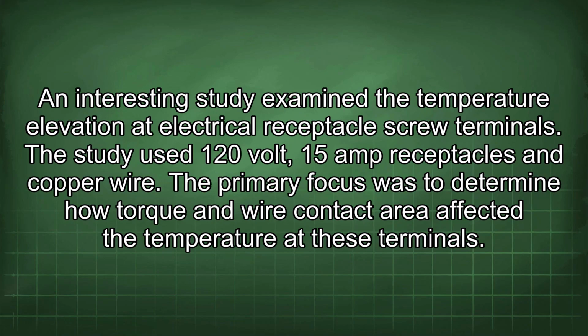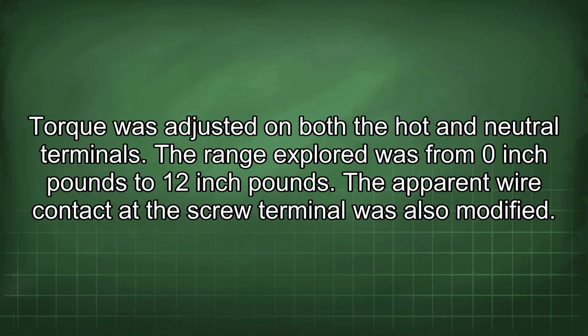An interesting study examined the temperature elevation at electrical receptacle screw terminals. The study used 120-volt, 15-amp receptacles and copper wire. The primary focus was to determine how torque and wire contact area affected the temperature at these terminals. Torque was adjusted on both the hot and neutral terminals. The range explored was from 0-inch pounds to 12-inch pounds.